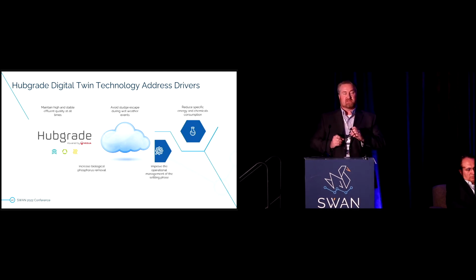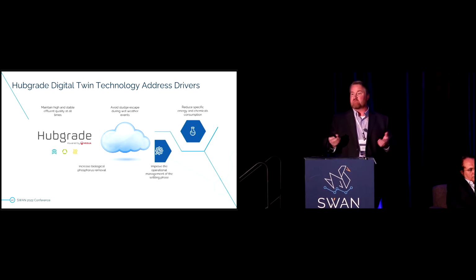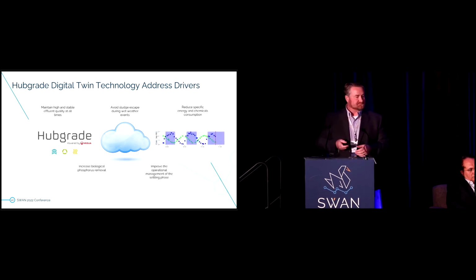And one thing that is kind of unique, we're not only gathering insights from the model predictions and using them to give insights to the operators, we're actively controlling all aspects of the system. Every 2 minutes, we're implementing a new DO set point, a new flow set point for a particular pump.